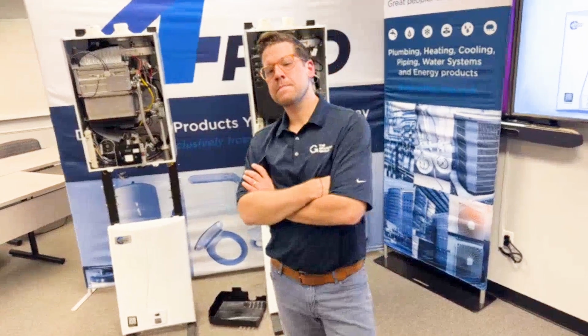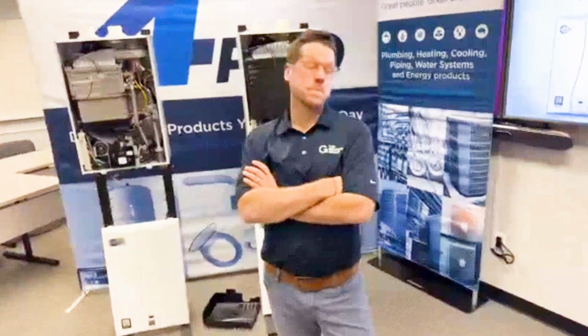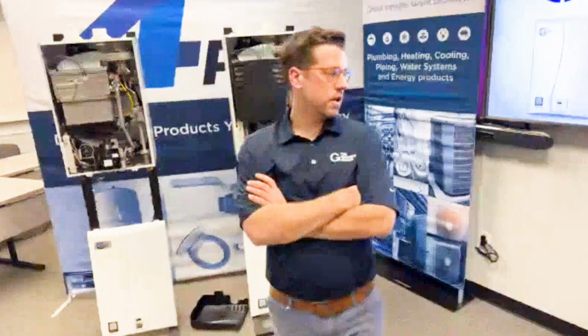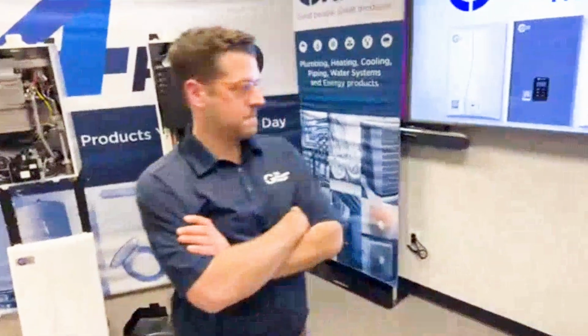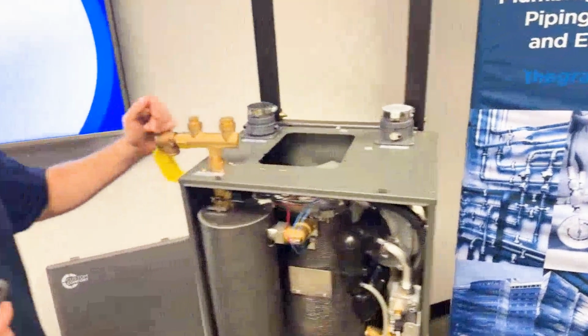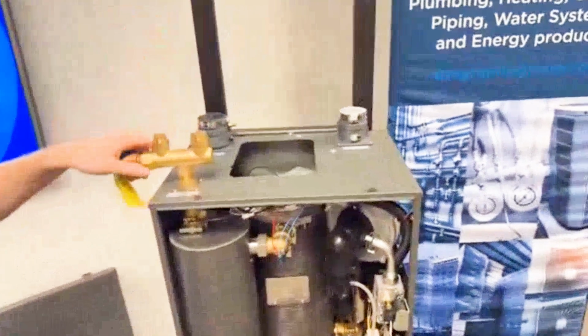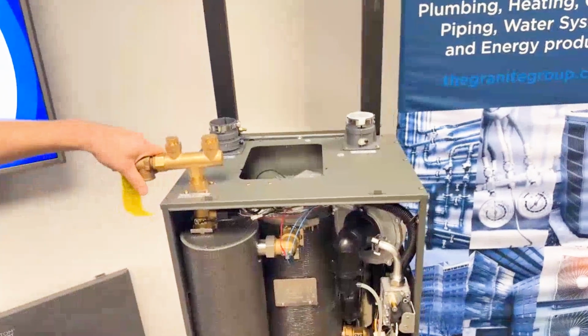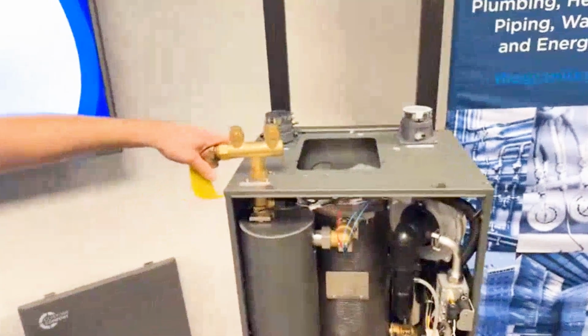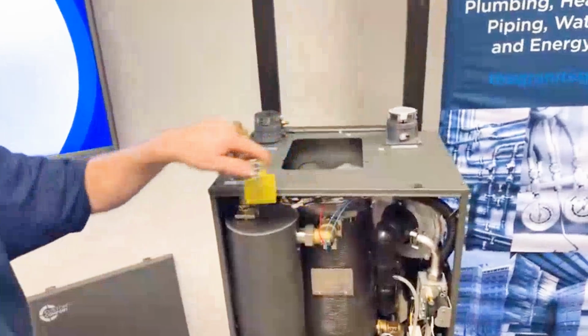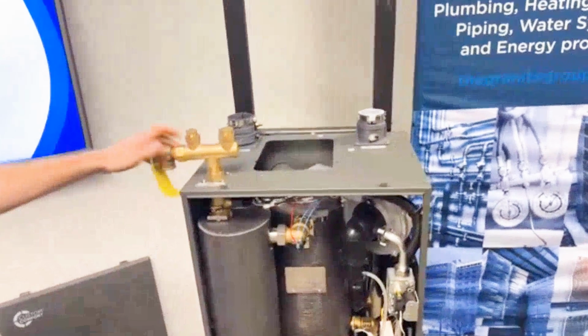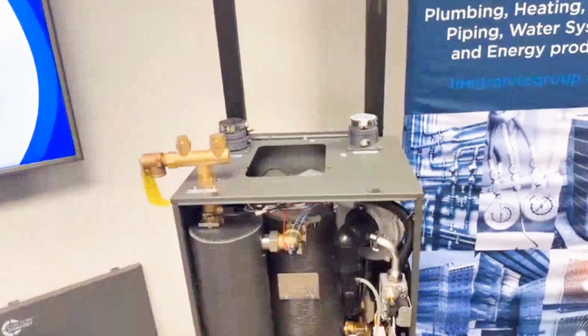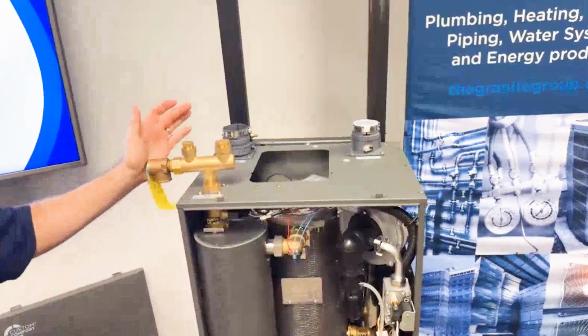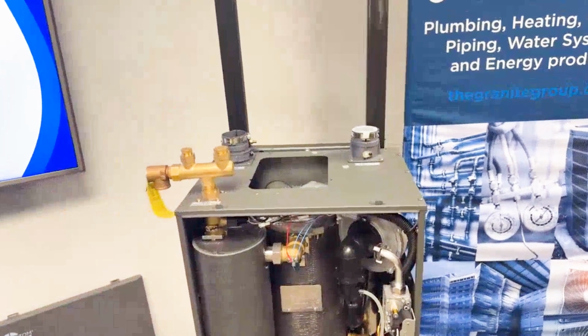Al asks about the relief valve shown there on top of the boiler. Can that be mounted vertically? I would say that is where we want the relief valve. If you came up with some additional fittings, you might be able to pipe something up, but I do appreciate Al bringing that up. I think I missed this when we were talking about the boiler. We give you this little Christmas tree manifold with the boiler, so that's another accessory that's included with it. You can throw an air vent on top here, and you've got the relief valve right off the top, just purging out any air that might be inside that buffer tank.